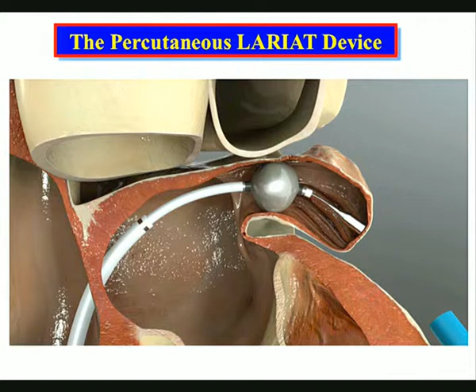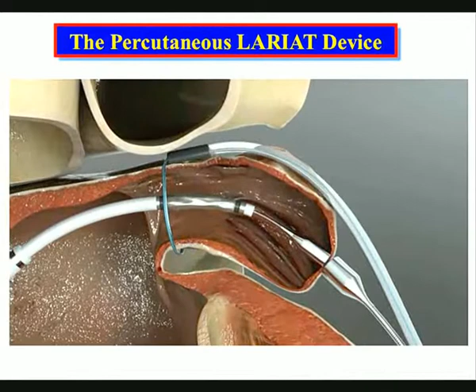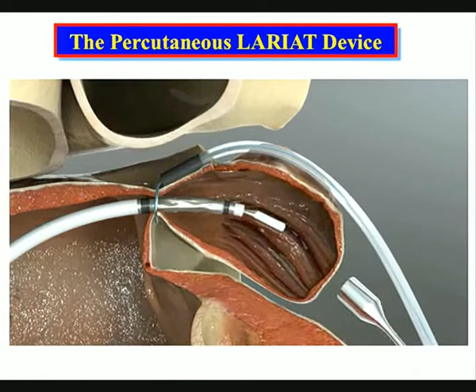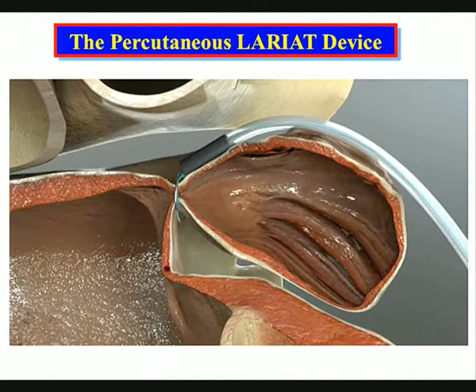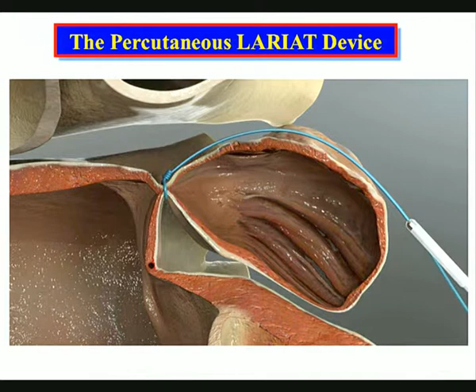And these magnets join one another. The Lariat is then passed across the catheter that's in the pericardium and slipped over the atrial appendage down to its base, and the balloon is blown up to guide the Lariat down. It's tightened down. There's a special tightening device that removes surgeon or operator variability, so it's tightened down to the same pressure all the time. The device is then removed from the inside and it's tightened down further, and then the Lariat's removed. And there's a device that's then passed over the end of the suture, and the suture is clipped, and it leaves it like that.